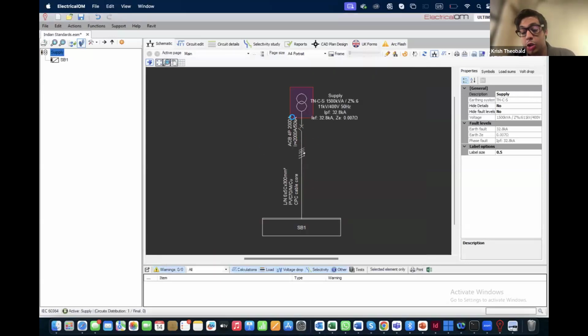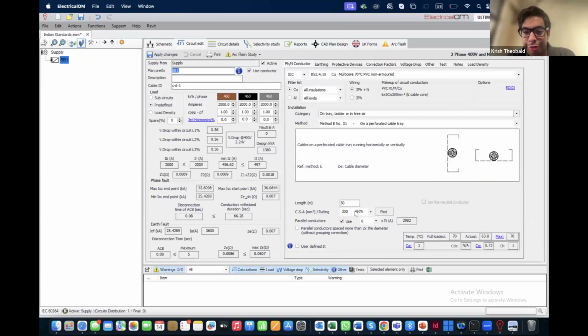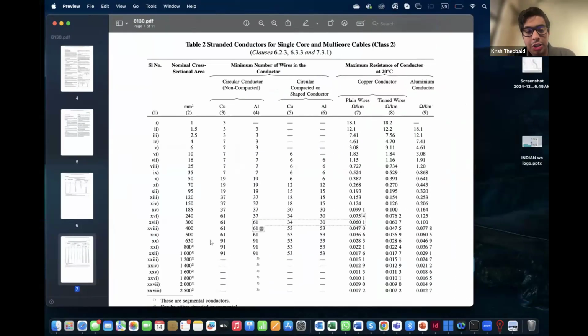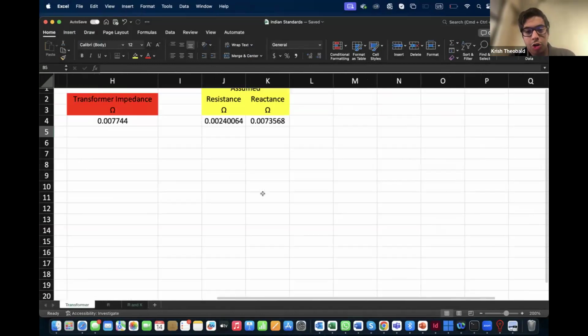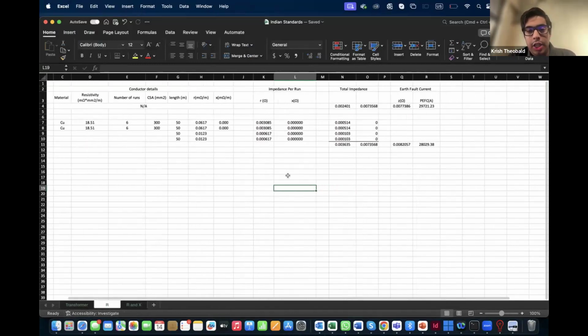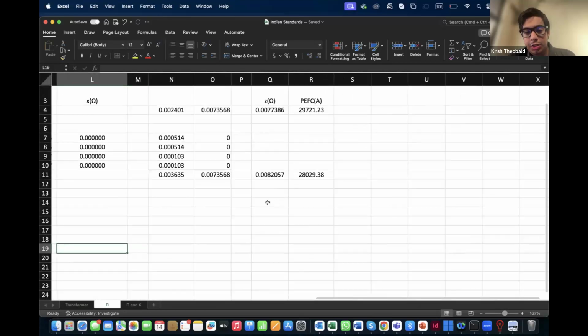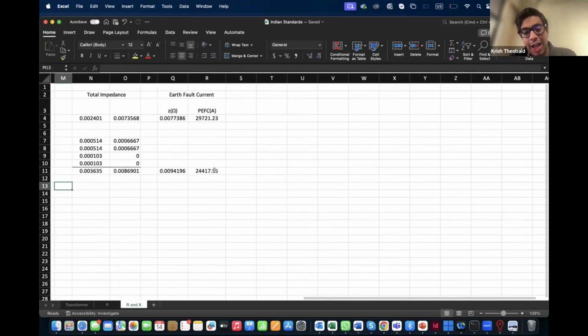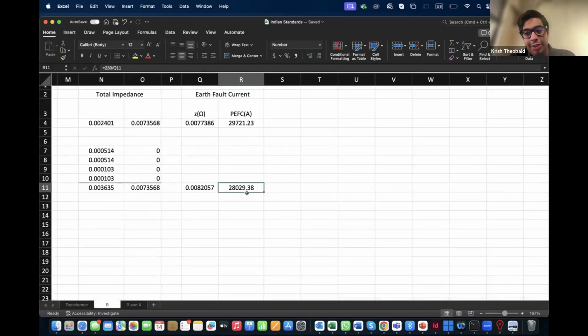I'll just show you how this is done manually as well. Then when we add our conductor, say 6 runs of 300 square millimeter copper multi-core conductor, we get a fault current. Now I'll show you on a spreadsheet. This is the transformer. If we only consider the resistance, we will get a value of about 28K at the end. However, when we consider the resistance and the reactance, we get a much lower value of 24K. So where a 25K device could have been used, you would have ended up with maybe a 50K or 36K device being used.